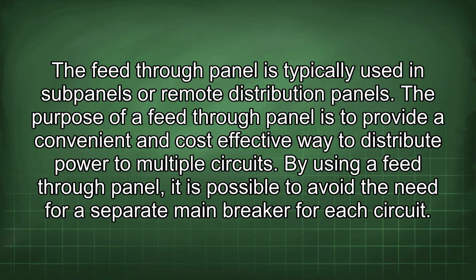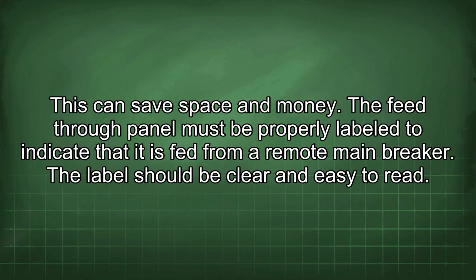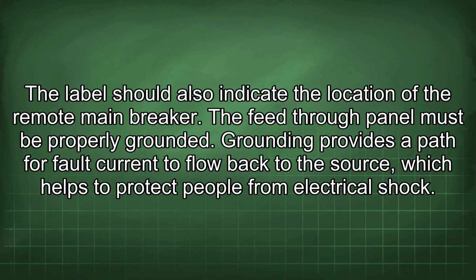The purpose of a feed-through panel is to provide a convenient and cost-effective way to distribute power to multiple circuits. By using a feed-through panel, it is possible to avoid the need for a separate main breaker for each circuit. This can save space and money. The feed-through panel must be properly labeled to indicate that it is fed from a remote main breaker. The label should be clear and easy to read. The label should also indicate the location of the remote main breaker.